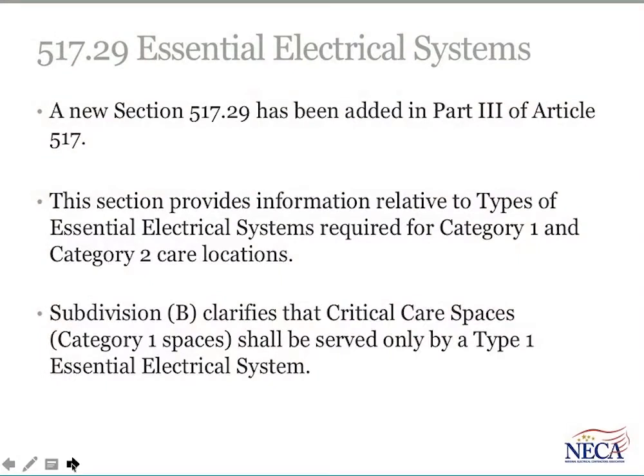Section 517.29 is new, and it provides an introduction to how the categories of essential systems are incorporated within the new Part 3, essential electrical systems. Category 1 and Category 2 type locations drive the requirements for Type 1 or Type 2 essential electrical systems. So the Category 1 and Category 2 locations are based on the level of care in those locations. The types of the essential electrical systems are derived from and aligned with NFPA 110, which gets into emergency or essential electrical systems that are categorized by type.